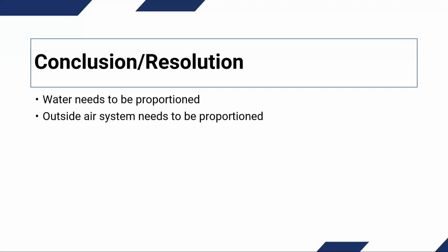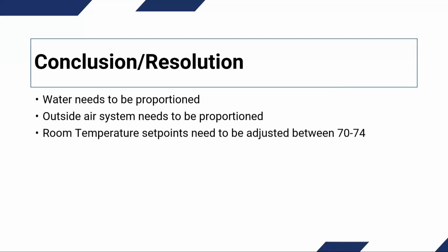Outside air is critical because we need to make sure that the building stays positive and that we're meeting the code requirements for ventilation. We typically request that the room temperatures get adjusted between 70 and 74. One of the common things that we see in buildings that have humidity problems, the first thing that gets done is the outside air usually gets shut, which results in a negative building, and the outside air is going to come in the building one way or the other, whether it's going through a piece of conditioned equipment or whether it's coming through the doors and any other place that air can get if the building's negative.